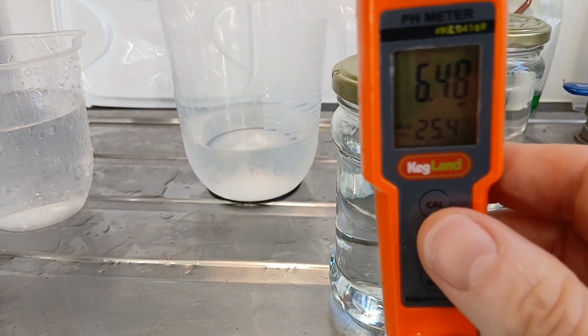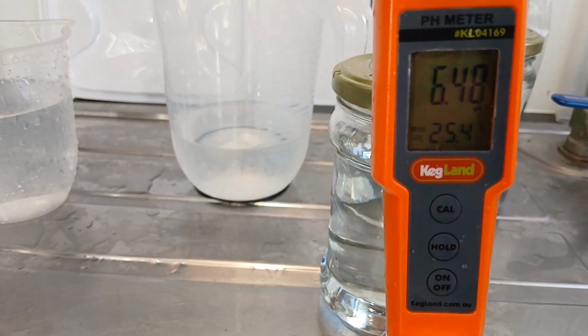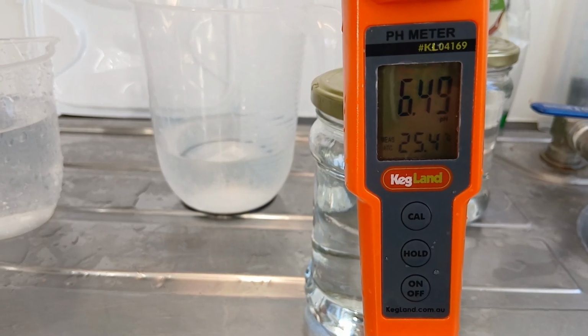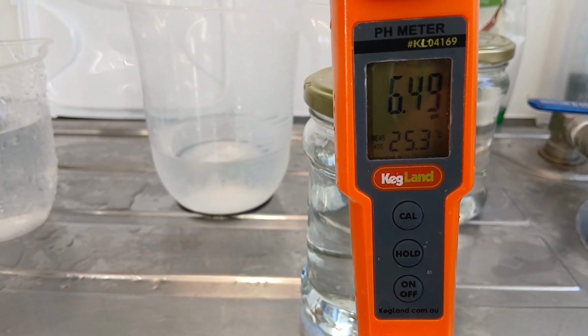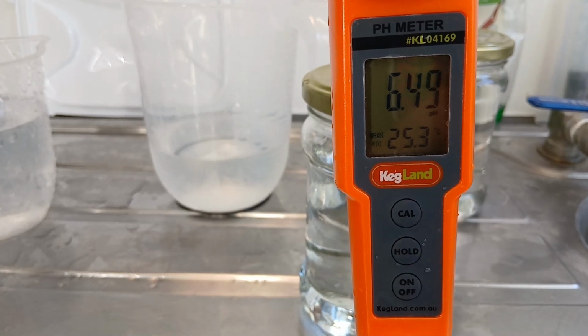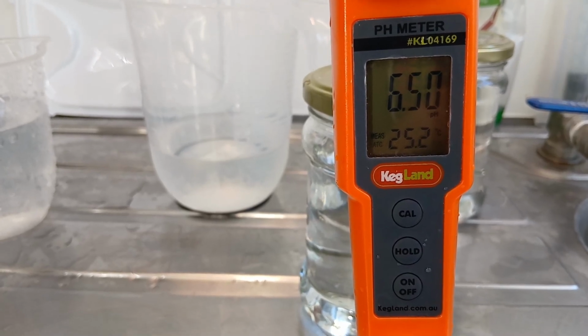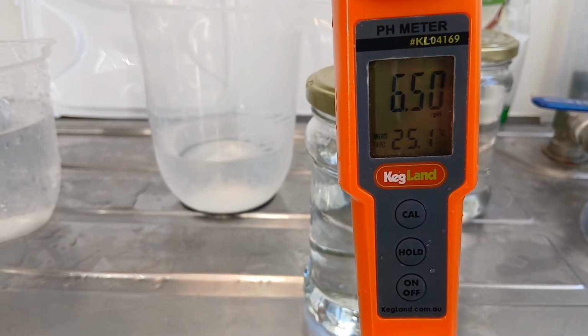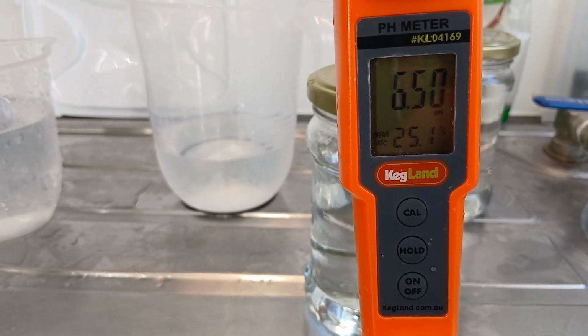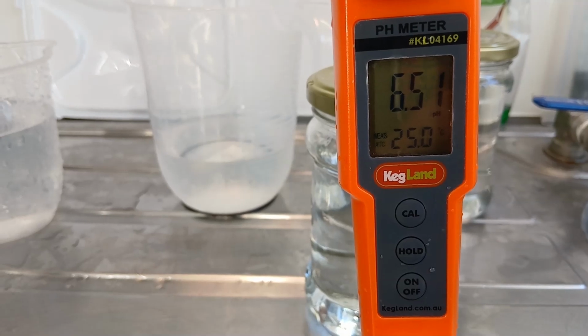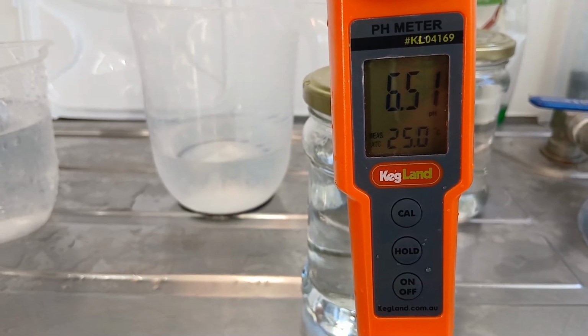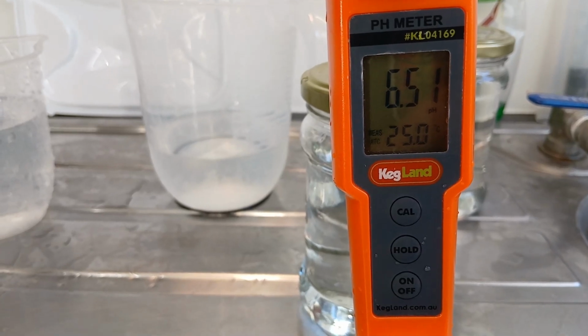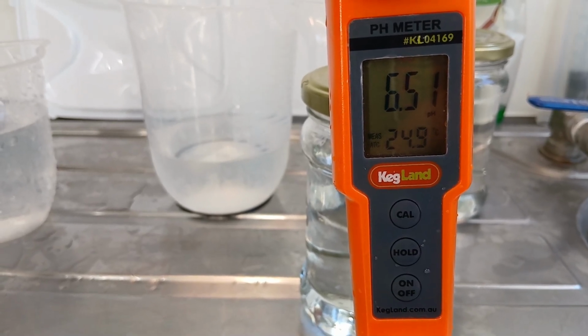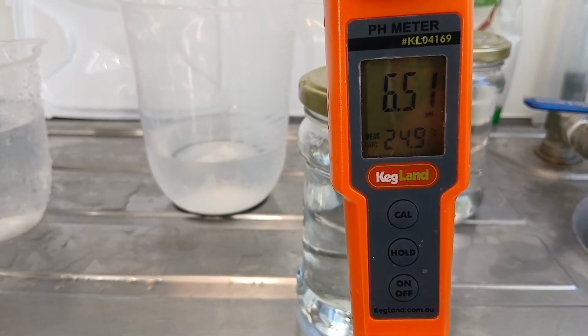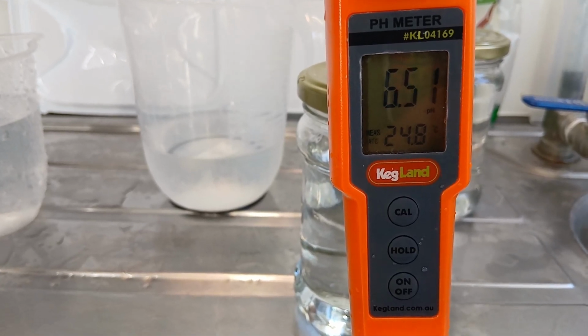I am expecting some calibration to be required because we've made some adjustments. Now this meter has ATC, automatic temperature compensation. That's only a temperature compensation for calibration and not for measurements. That is something that needs to be borne in mind when using pH meters with automatic temperature compensation. From as far as I'm aware, it's only applied in the calibration process and not for measurements.